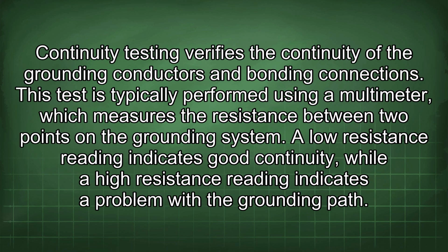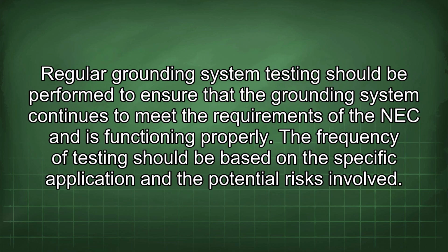Continuity testing verifies the continuity of the grounding conductors and bonding connections. This test is typically performed using a multimeter, which measures the resistance between 2 points on the grounding system. A low resistance reading indicates good continuity, while a high resistance reading indicates a problem with the grounding path. Regular grounding system testing should be performed to ensure that the grounding system continues to meet the requirements of the NEC and is functioning properly.